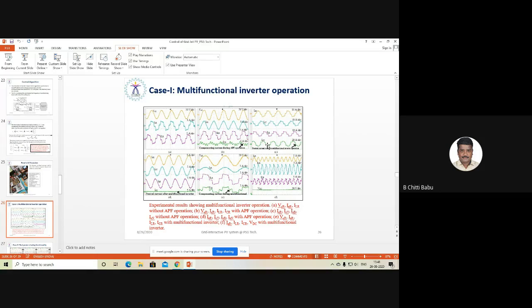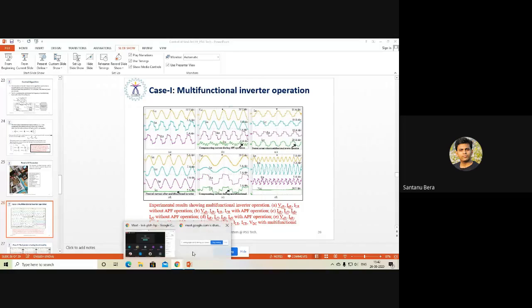Anyway, for neutral current compensation or harmonic current, you should have fundamental knowledge of the symmetrical component theory in power systems. Are you from power electronics or power systems? Power electronics, sir. So if you are able to study power systems, please study symmetrical components, power system analysis, or power system faults. Please go through what happens when the grid is under fault, how you linearize the parameters, and how the harmonic components are involved. I mean positive sequence, negative sequence and zero sequence. You will completely understand what third harmonic is, what zero sequence is, what positive sequence is, and what negative sequence is. As you are from a power electronics background, maybe you may not have an idea about zero, positive and negative sequence. Okay, sir. Thank you so much, sir. Thank you for such a session. Okay.